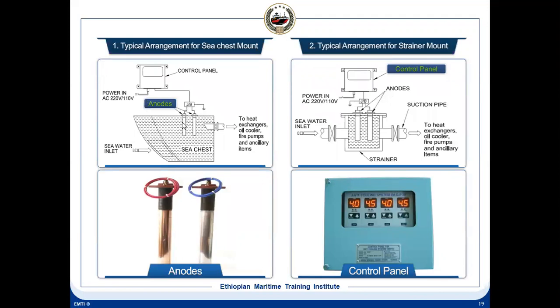It's only the positive cable, only positive is connected with this anode. You can see this cable here, and the negative is through the ground. And these current settings are very important. You can change these current settings. If you set a very high current, then it will finish up the anode at a much faster rate. So always currents are set as per the manufacturer's instructions. Normal life is around 1.5 years. And normally seagoing current is 5.5 amps for the copper anode. The anode current is slightly lesser than the aluminum one, Tc1, trap corrosion anode.